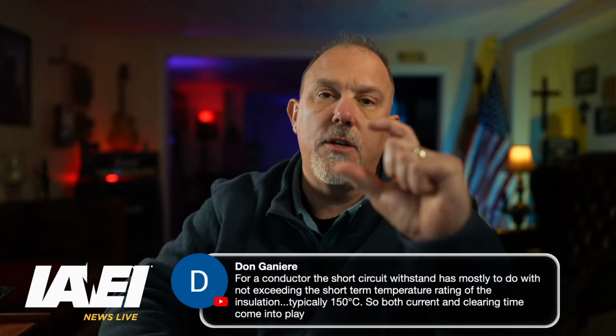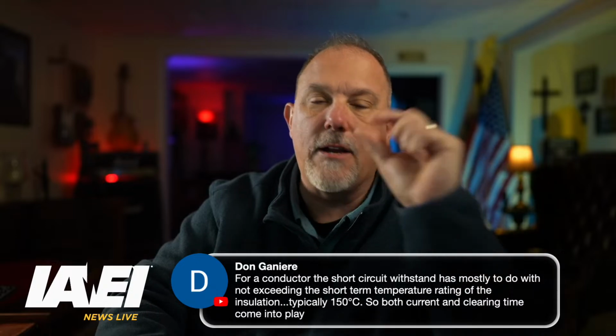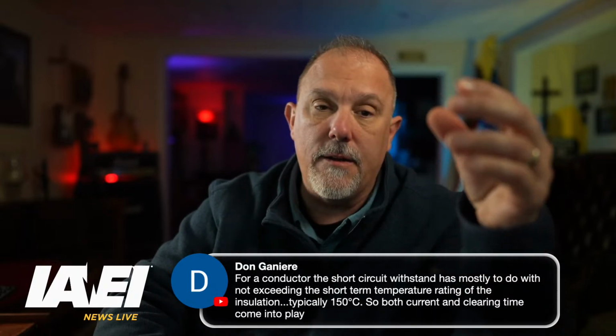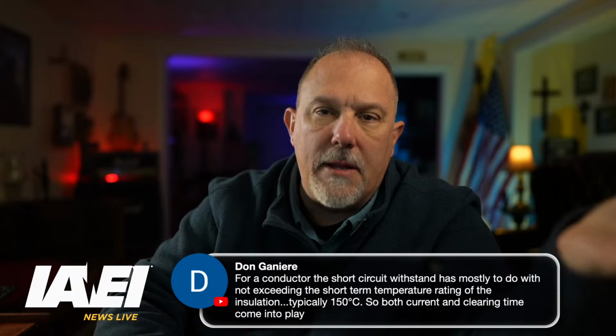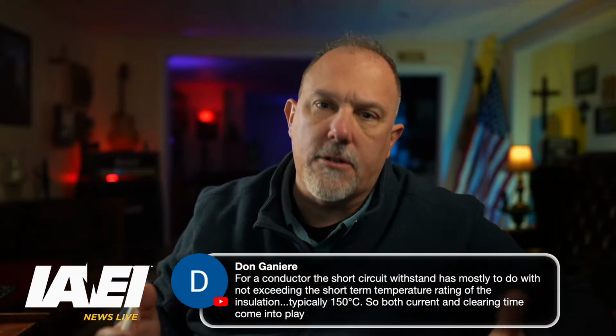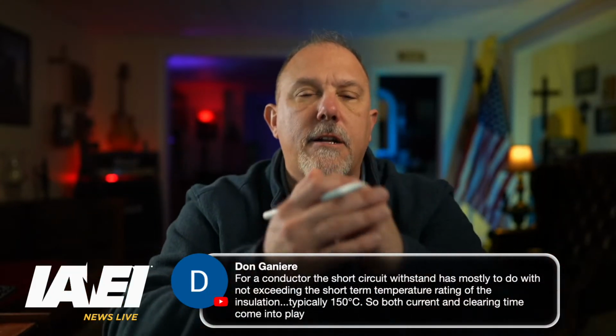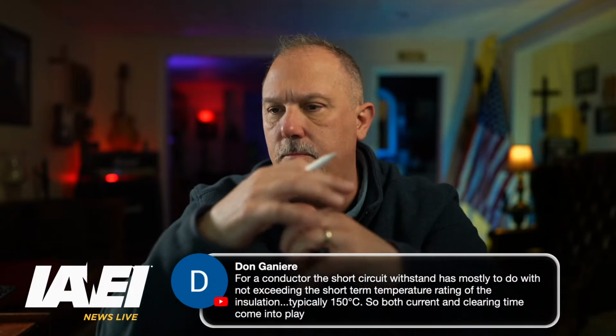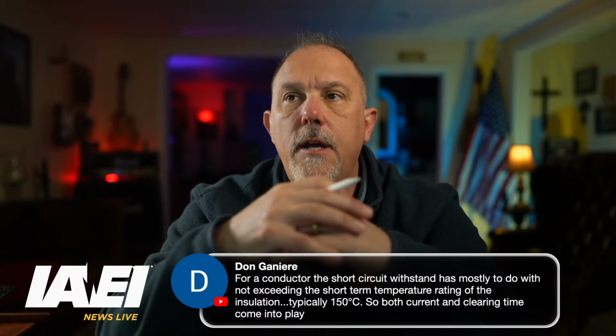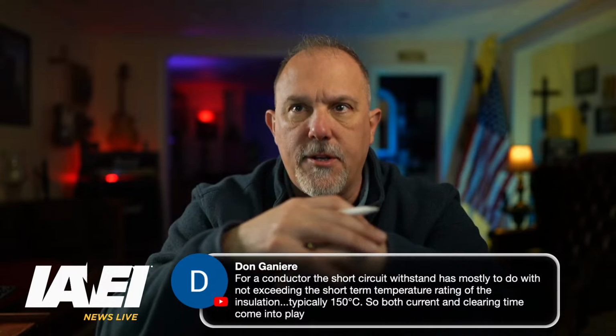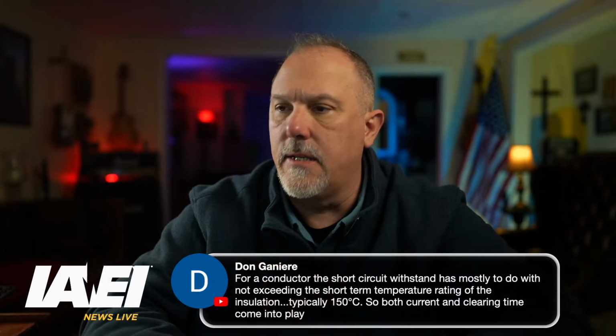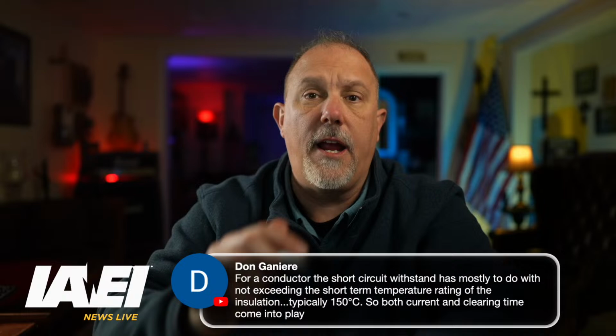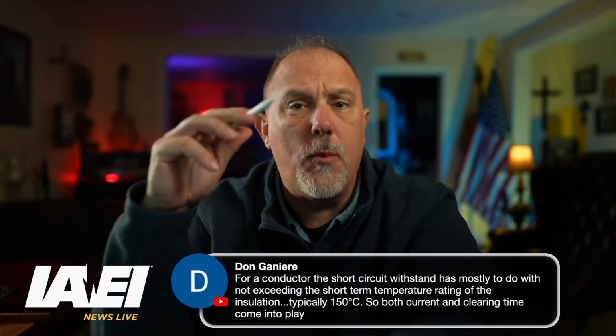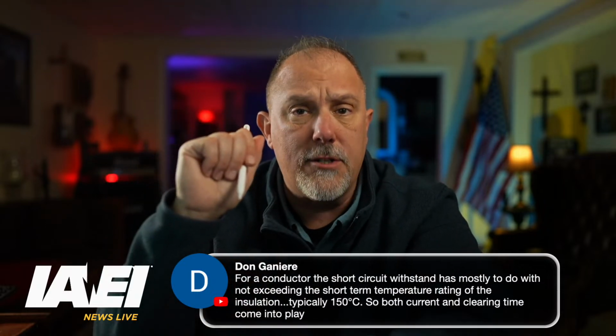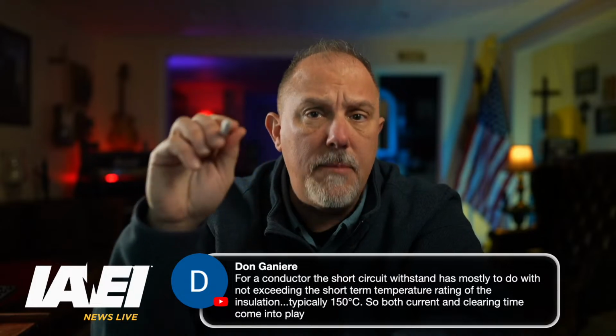a conductor has an insulation, like a rubber or a compound. It depends on the conductor that you select. That conductor is going to get hot, and what we don't want to do is melt that insulation. So the damage curve has to take that insulation into consideration, and there are temperatures for the equation that's in the National Electrical Code. You'll see some key parameters for that information.